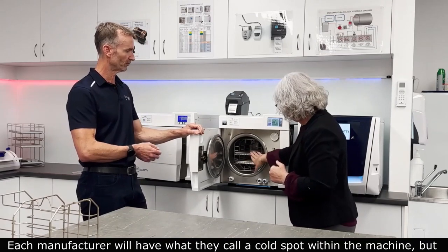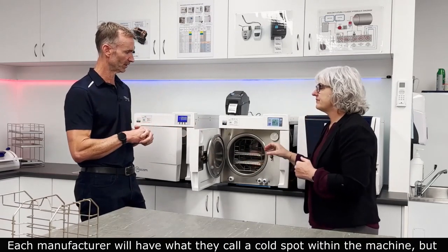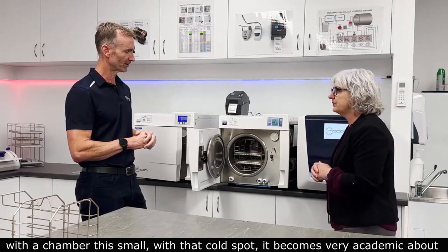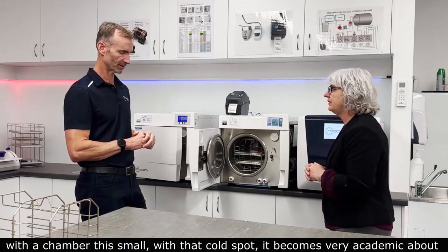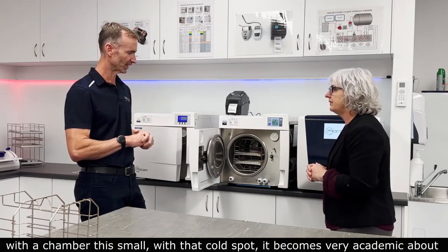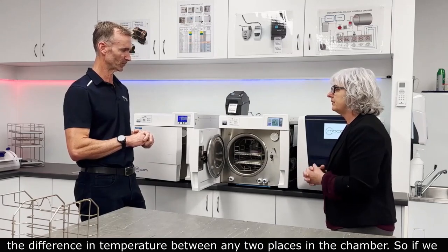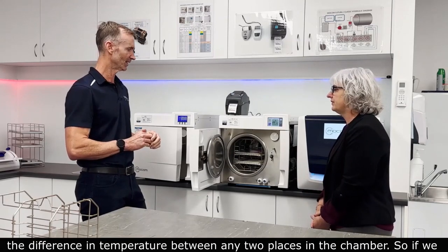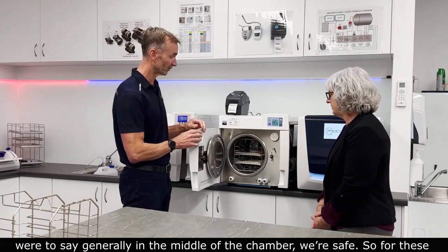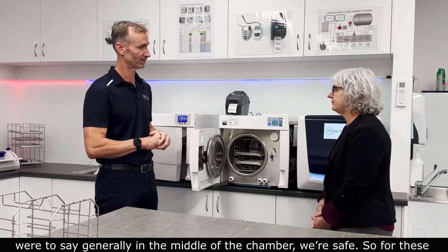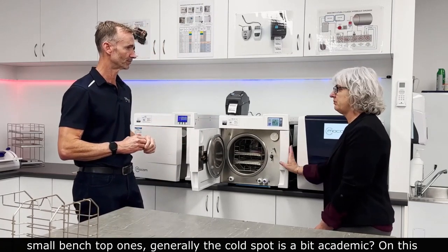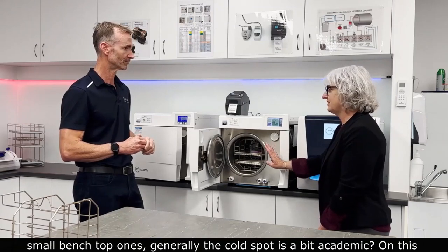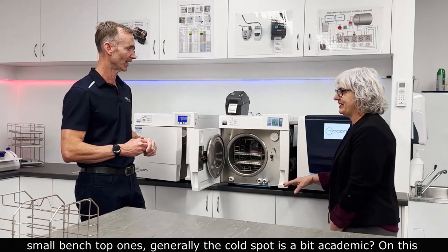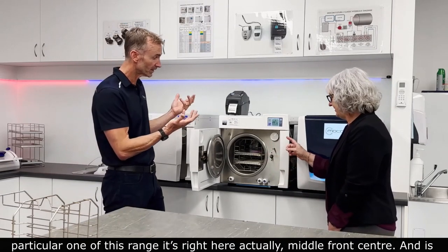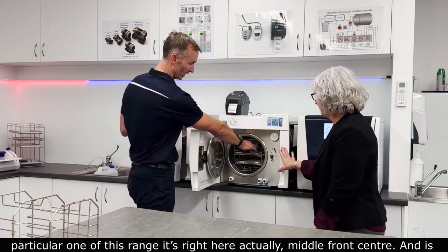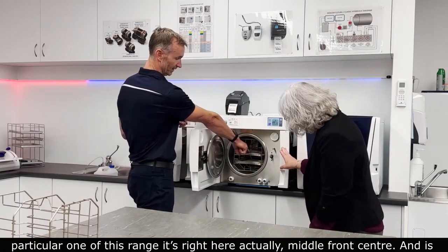Each manufacturer will have what they call a cold spot within the machine, but with a chamber this small, the cold spot becomes very academic about the difference in temperature between any two places in the chamber. So if we were to say generally in the middle of the chamber, we're safe. For these small benchtop ones, generally the cold spot's academic. On this particular range, it's right here actually, middle, front, centre.